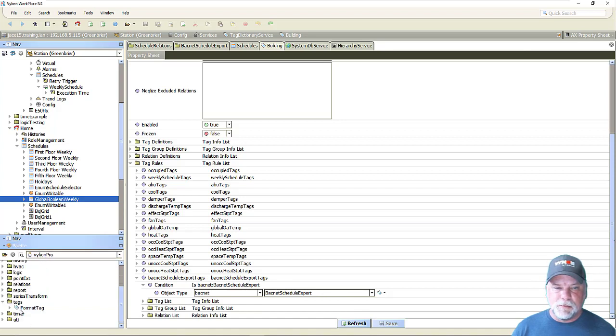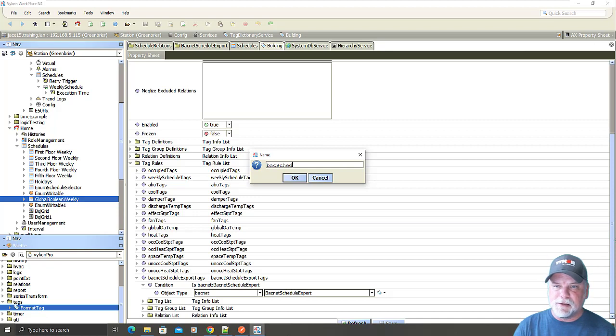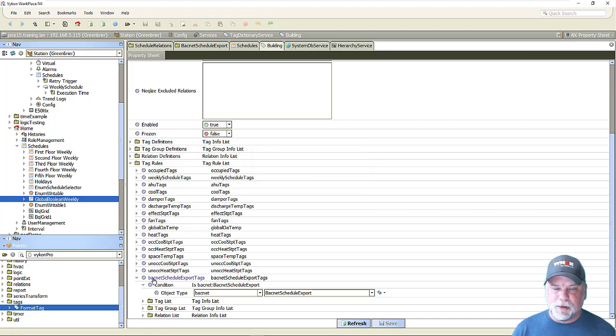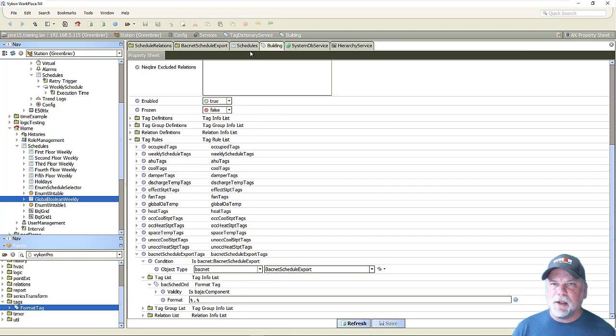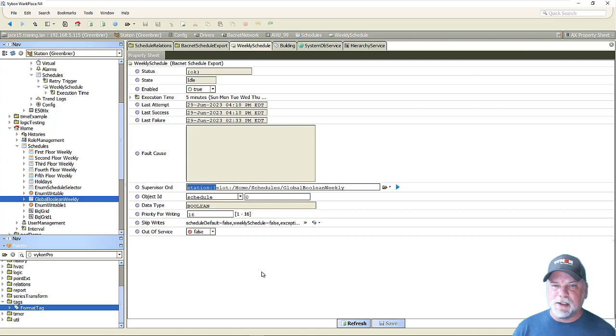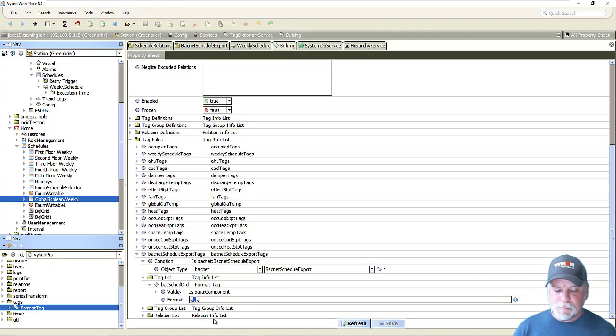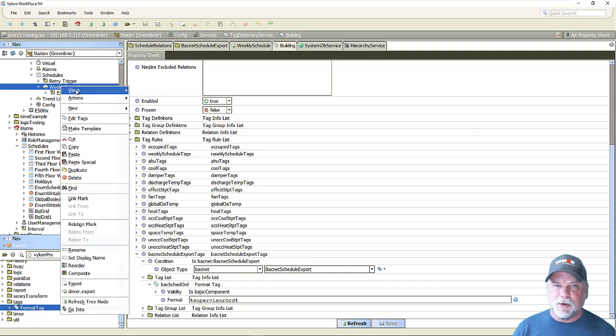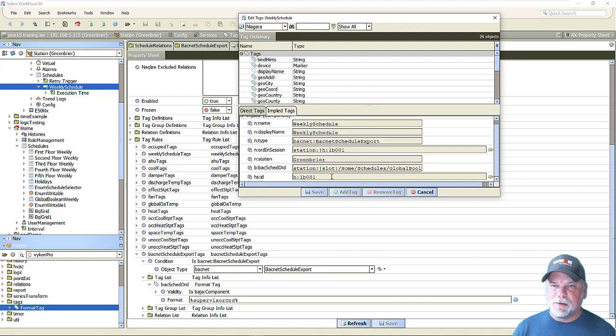Going back to my Vykon Pro palette, I can select the format tag and drop it onto the tag list. In this case, I'm going to assign the tag ID 'backsched ord' to the schedule export component. Looking at that schedule export property sheet, there's a supervisor ord property which stores the ORD to the schedule that's being exported from the station to the BACnet device. One key thing to note is that that ORD actually includes the 'station colon pipe' scheme, where the slot path of the schedule itself only started with 'slot colon'. On this tag with the B format, we can use the supervisor ORD property to assign that tag to the weekly schedule component. When I look at that tag, we'll see the backsched ord tag but it includes that leading 'station colon pipe'.